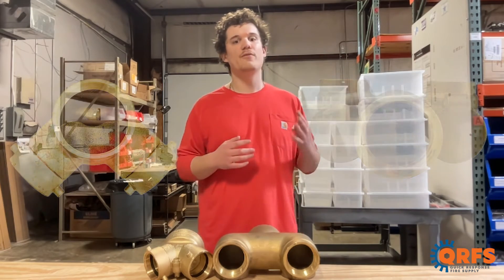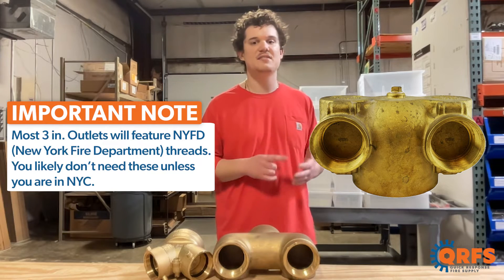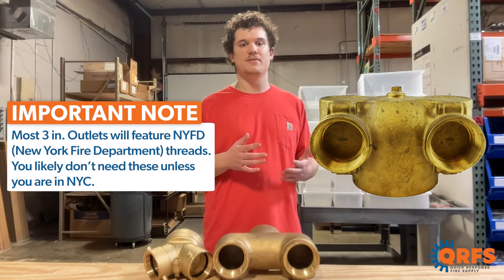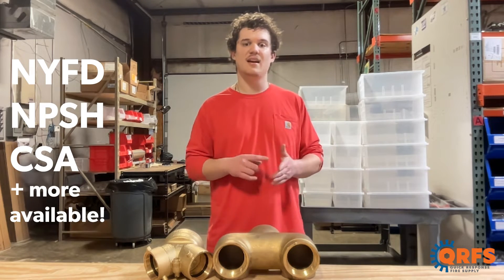FDCs typically feature one 4-inch national pipe thread, also known as NPT, outlet and two 2.5 or 3-inch national standard thread, also called NST or NH, inlets. There are other inlet threading options available such as NYFD, NPSH, and CSA, and more.